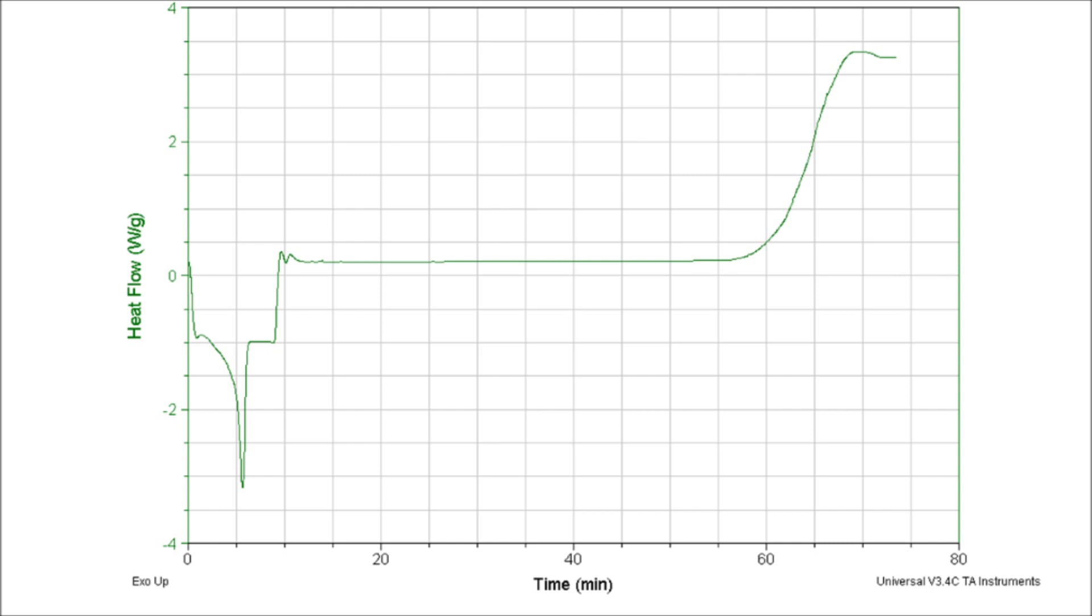Fast forward about an hour to the conclusion of the standard OIT test we were running. Here is the curve produced by the DSC software. As you can see, it very closely resembles that of the OIT reference curves we saw earlier. We know the T sub 0 is 13.93 minutes, but we must now determine the T onset point, as both values are needed to calculate the OIT.